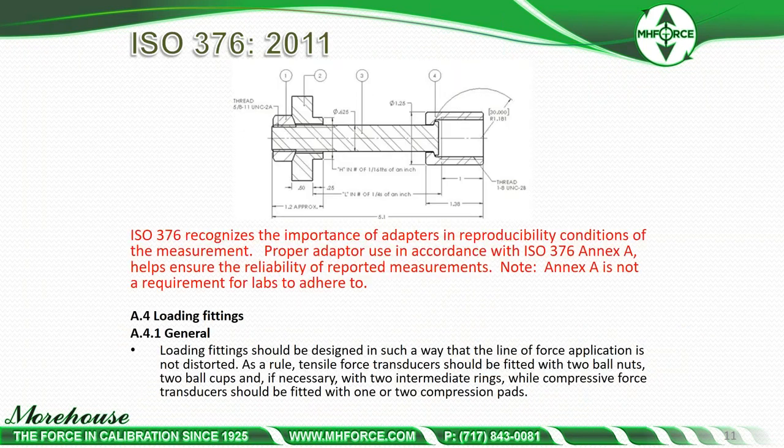ISO 376 recognizes the importance of adapters and reproducibility conditions of measurement. Proper adapter use in accordance with ISO 376 Annex A helps ensure the reliability of reported measurements. Annex A is not a requirement per se, but it is good practice for anyone making force measurements — whether ISO 376, ASTM E74, or general measurements. Having the right adapters is critical to ensuring repeatable results.